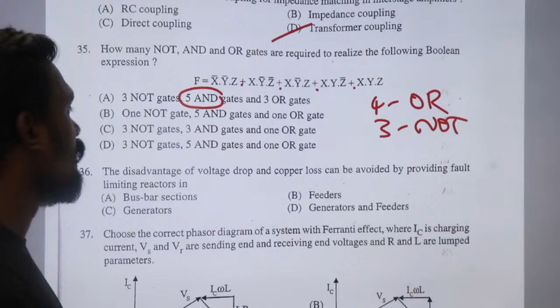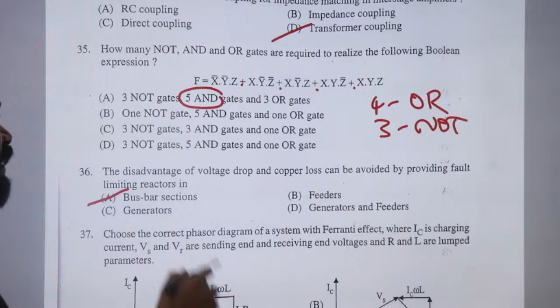Next question, this is the 36th one. Ramana sir gave me that the answer is option A. The disadvantage of voltage drop and copper losses can be avoided by providing the fault limiting reactor in the bus bar section. If we add it in the bus bar section, we can avoid that.